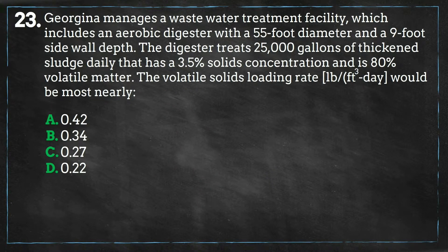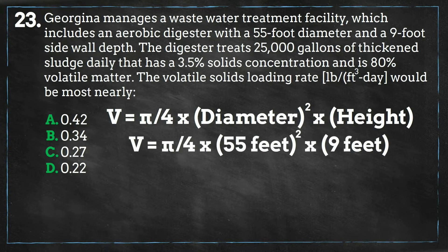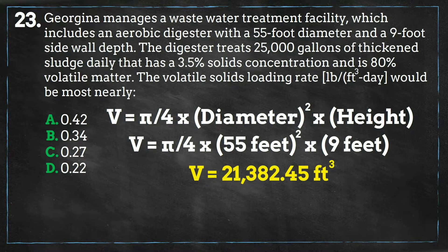To solve this problem, we need to solve for the daily volumetric flow rate of volatile solids as well as the volume of the digester. We have the dimensions of the digester, and knowing the volume calculation will be the cross-sectional area of the digester multiplied by its height. We can solve for this and we get a volume of 21,382 cubic feet.